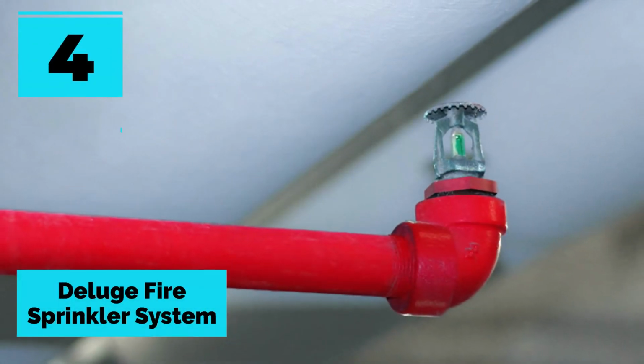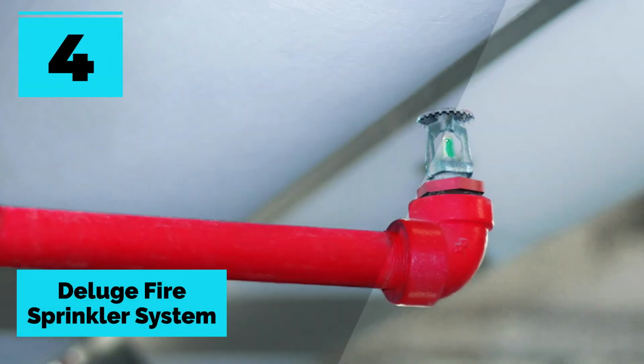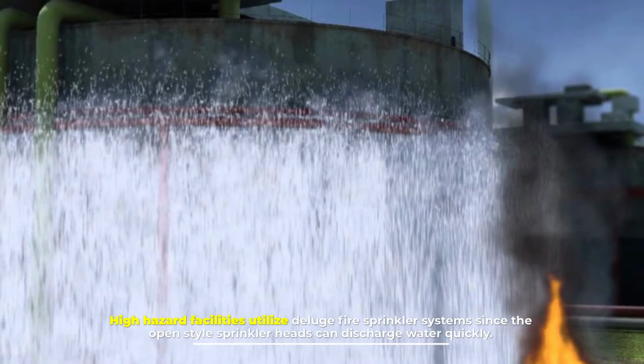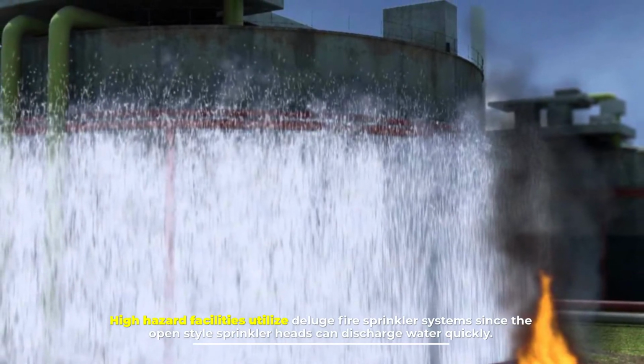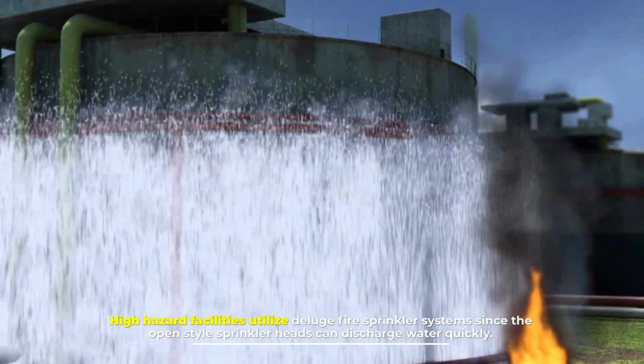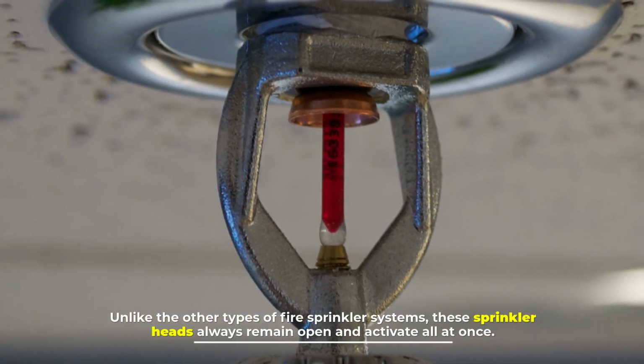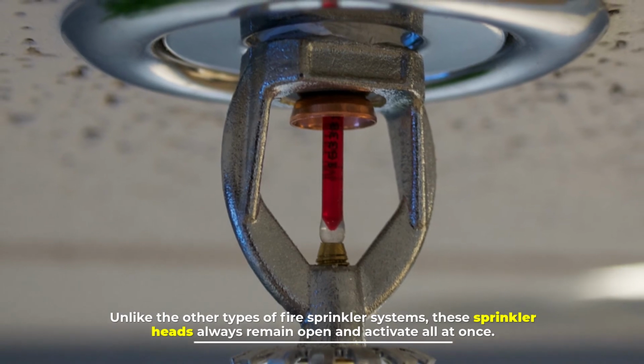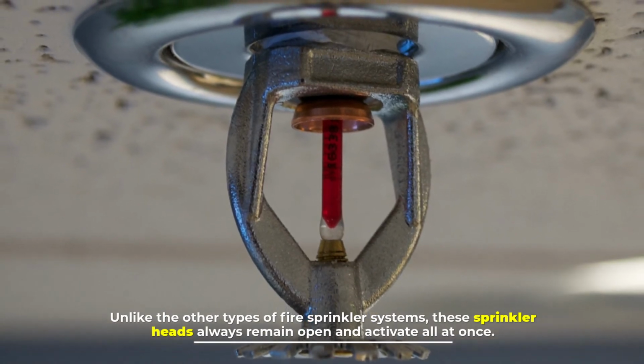Number 4. Deluge fire sprinkler system. High-hazard facilities utilize Deluge fire sprinkler systems since the open-style sprinkler heads can discharge water quickly. Unlike the other types of fire sprinkler systems, these sprinkler heads always remain open and activate all at once.